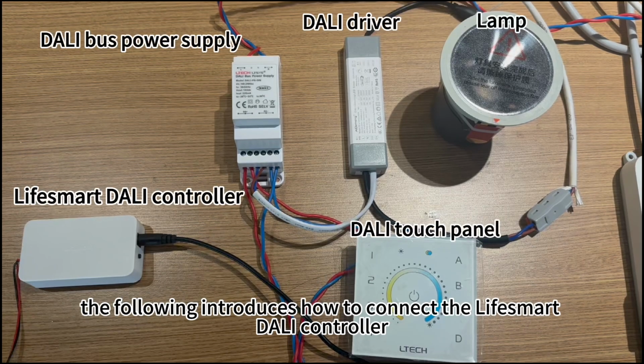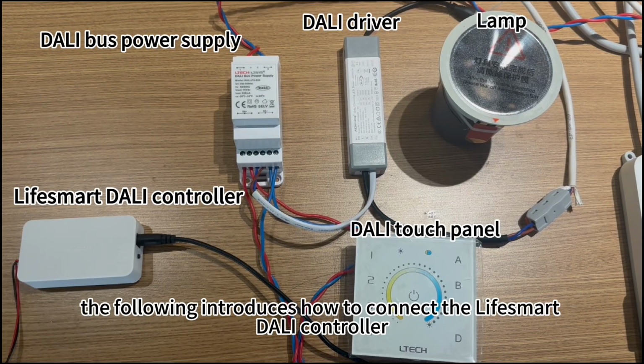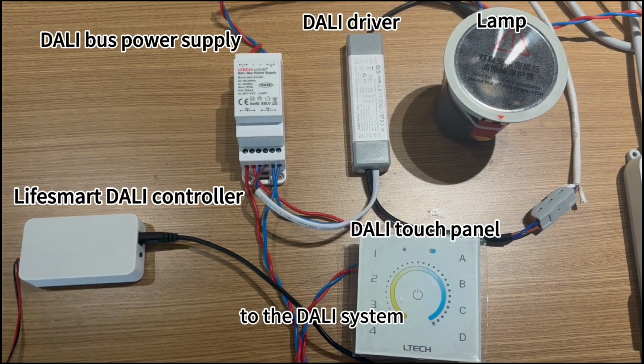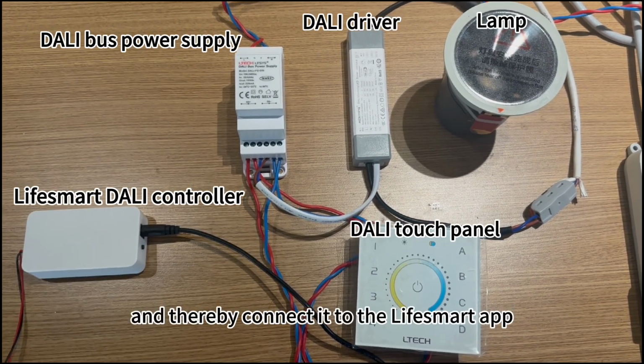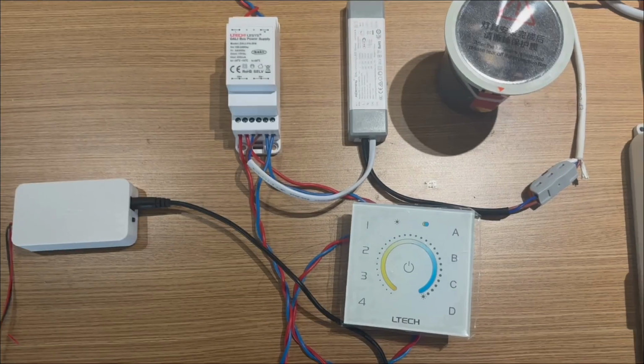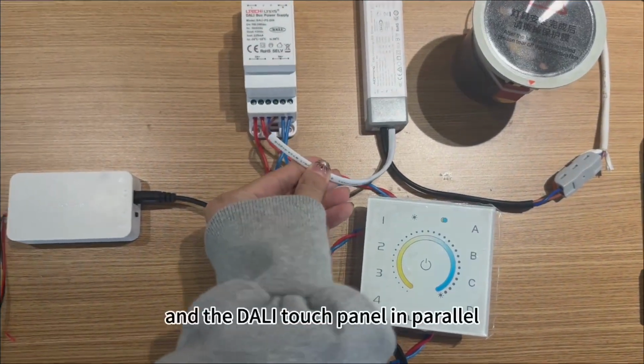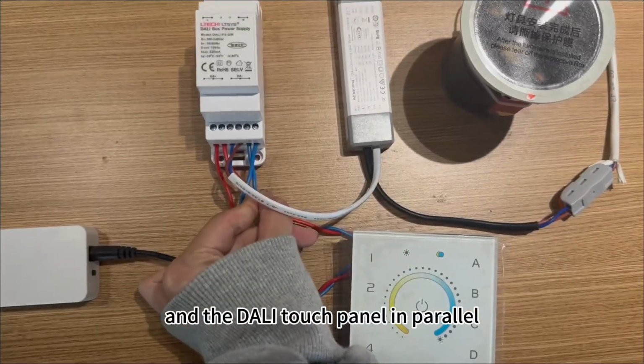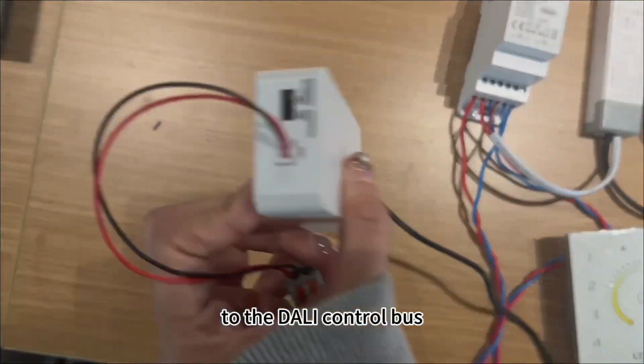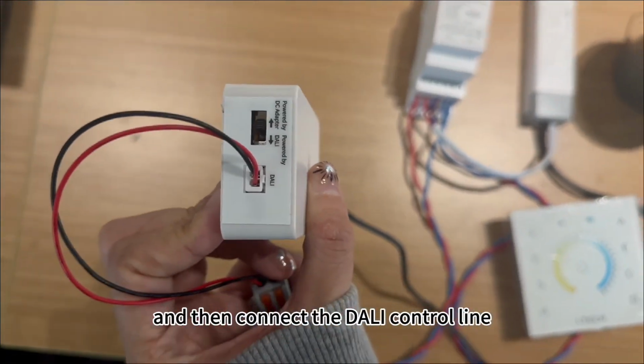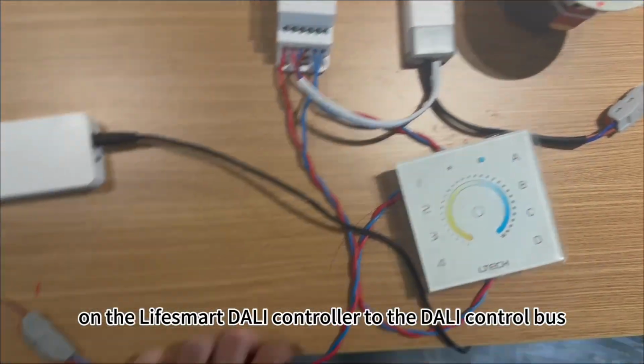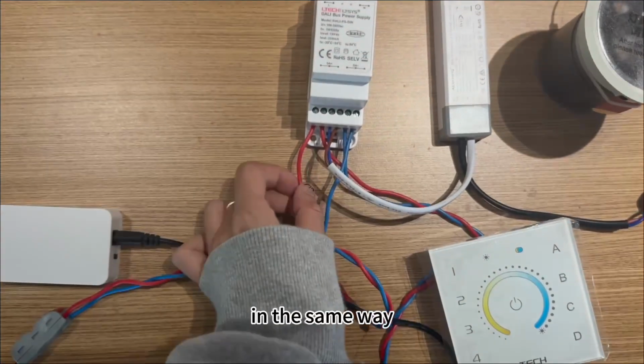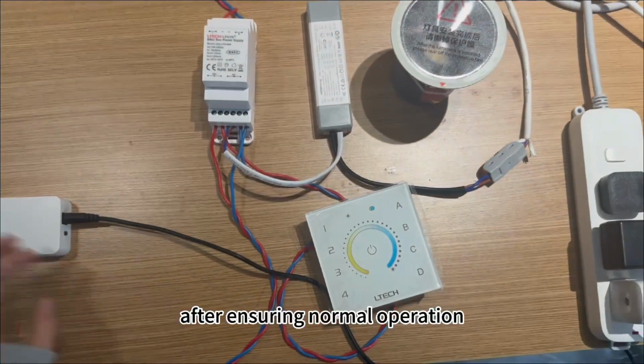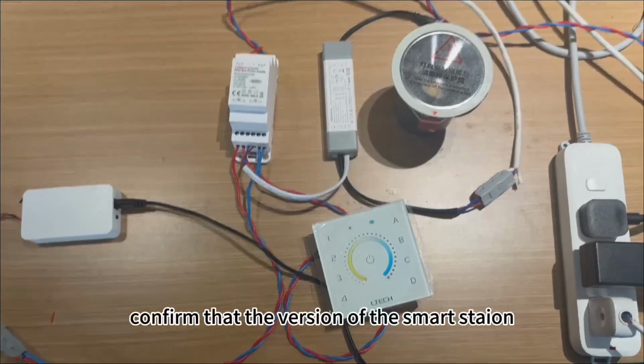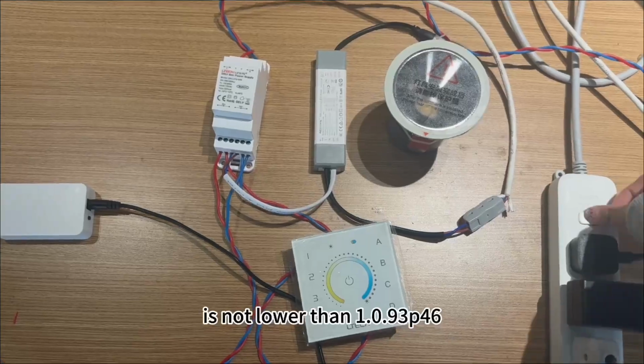The following introduces how to connect the LifeSmart DALI controller to the DALI system and thereby connect it to the LifeSmart app for control. Connect the DALI driver and the DALI touch panel in parallel to the DALI control bus, and then connect the DALI control line on the LifeSmart DALI controller to the DALI control bus in the same way.